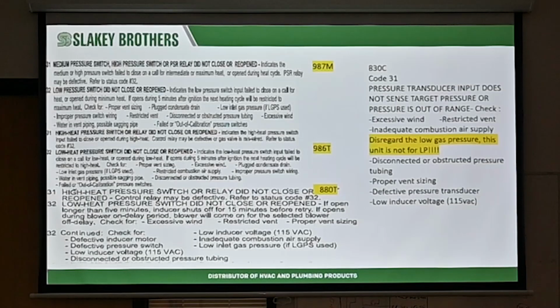So we're going to talk through, when you got a problem with one of those switches, what to look for on the pressure switches themselves. On a high efficient furnace, evolution or non-evolution, the most common thing that will cause a pressure switch to not close, to not work properly, is water, moisture. Okay? And moisture usually doesn't happen right away, it'll happen later.